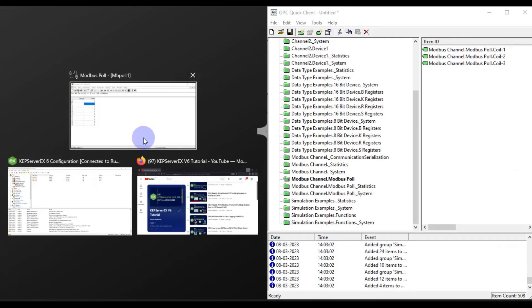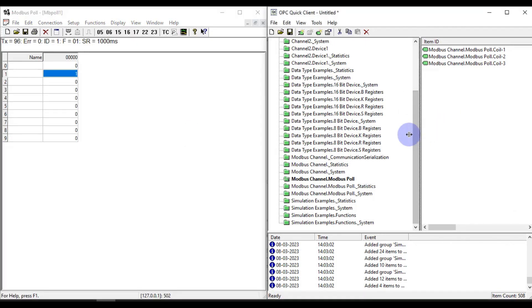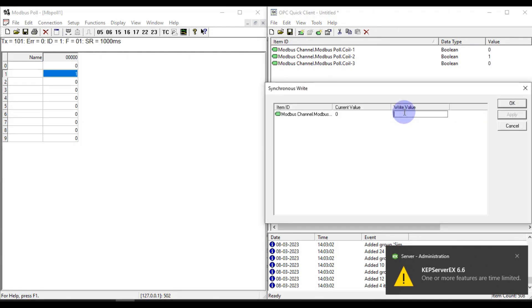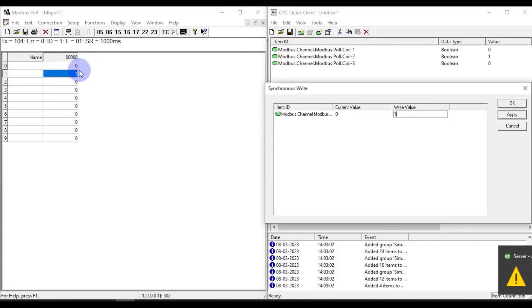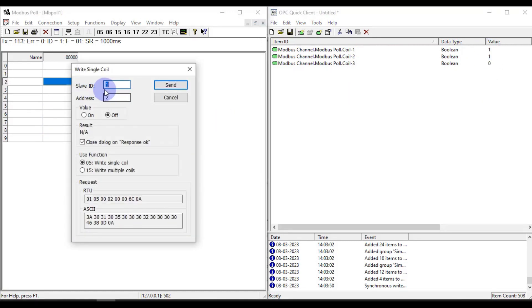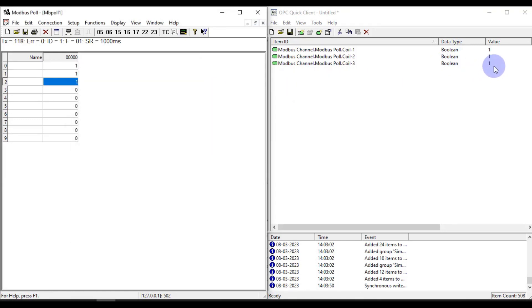Now if I want to write from KEPServer, I can open it in parallel. Right-click and select Synchronous Write. I want to type a value of 1 — right now it is zero, but I want to change it to 1. Press OK and you can see the value is 1, and it reflects in Modbus Poll. To verify the other direction: set slave ID 1, address 2, value On, and send. You can also check the value is reflecting here.